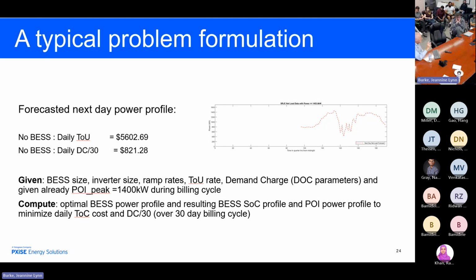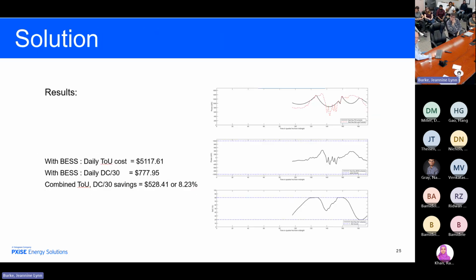This is done, as I said, every 5 minutes, and it's important, obviously, that the optimization completes in 5 minutes. Now, we run on little SEL 3355 computers, so we have to be aware that the SEL computer is not only doing real-time control 60 times a second, but it's also solving this optimization problem. So we are acutely aware that we may not have enough computing cycles, and we're doing some research on ways to speed this up and to use some improved optimization algorithms. And I'm certain from what I've seen, you guys are already doing that. So let's keep that up. This is the result. We're only saving about 10% here, but this gives you the optimal profile for the day ahead.